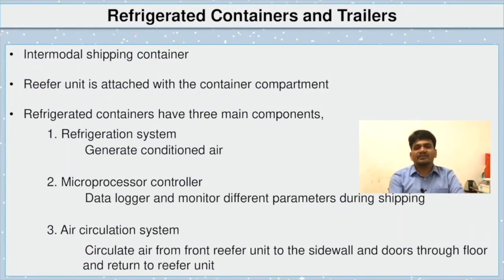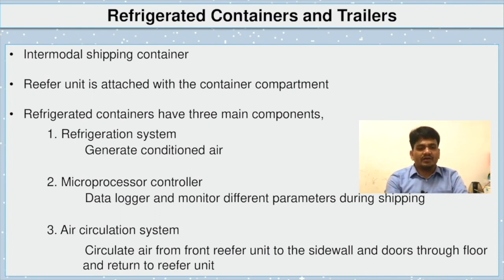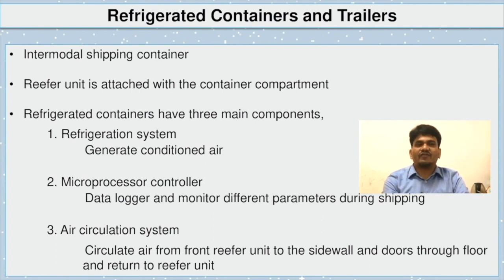Refrigerated containers and trailers — in an intermodal shipping container, the reefer unit is attached with the container compartment. Refrigerated containers have three main components: first, the refrigeration system which generates conditioned air; second, a microprocessor controller with a data logger that monitors different parameters during shipping; third, the air circulation system, which circulates air from the front reefer unit to the sidewall and doors through the floor and back to the reefer unit.